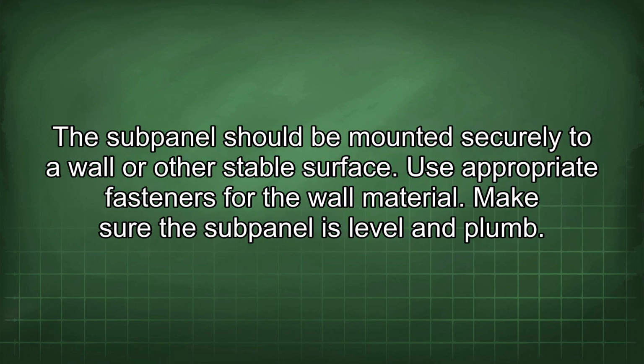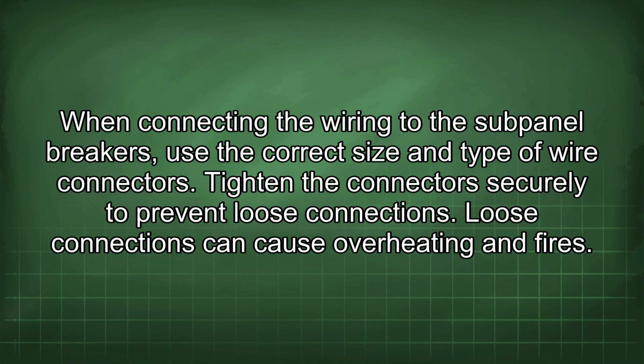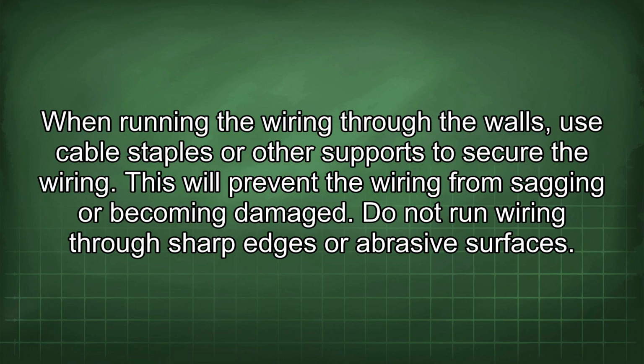The subpanel should be mounted securely to a wall or other stable surface. Use appropriate fasteners for the wall material. Make sure the subpanel is level and plumb. When connecting the wiring to the subpanel breakers, use the correct size and type of wire connectors. Tighten the connectors securely to prevent loose connections. Loose connections can cause overheating and fires. When running the wiring through the walls, use cable staples or other supports to secure the wiring.